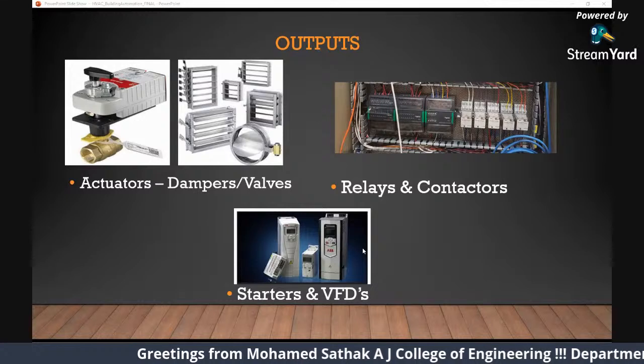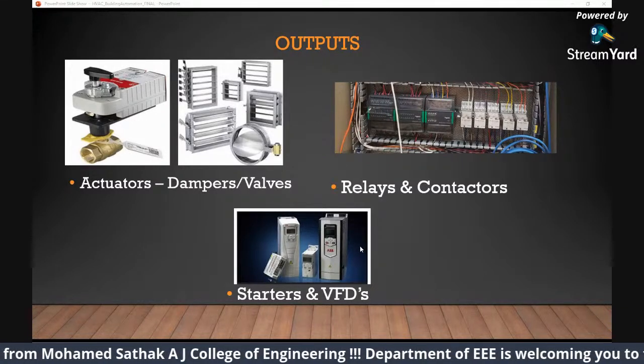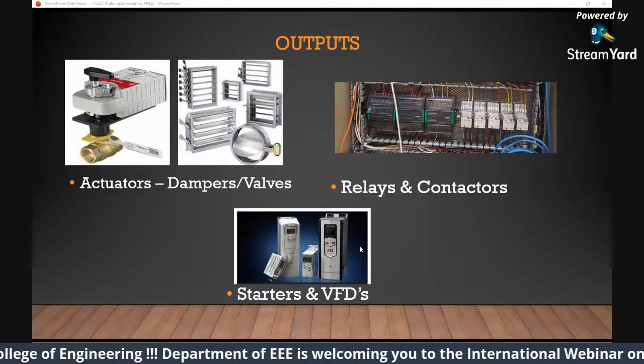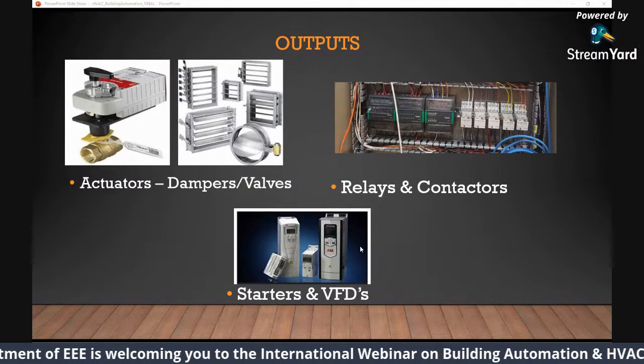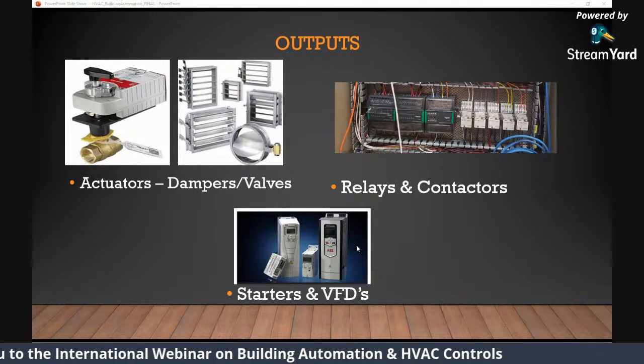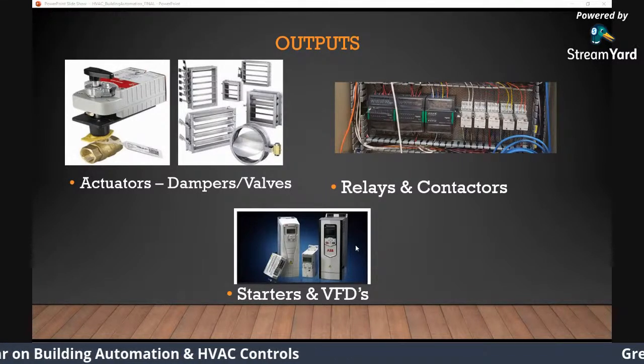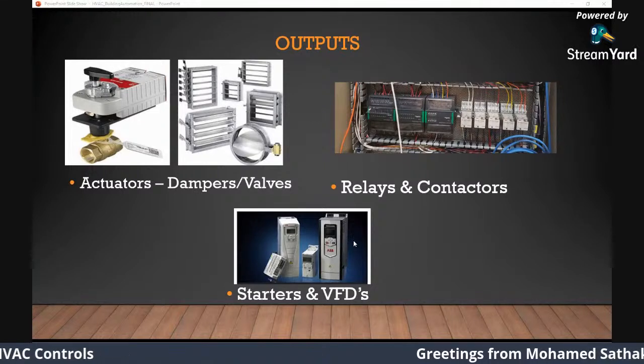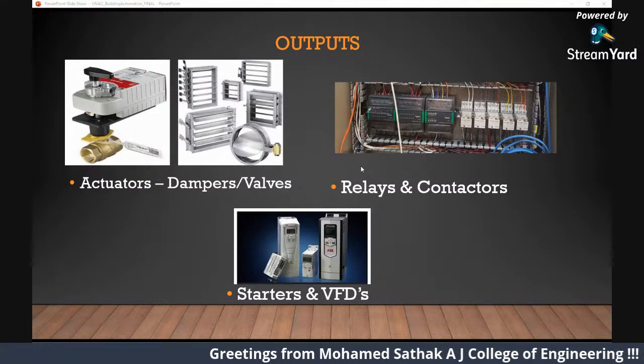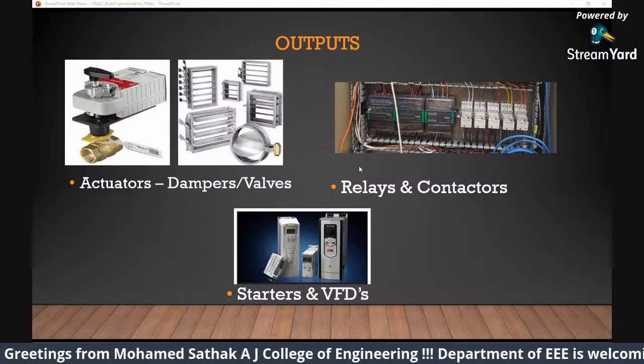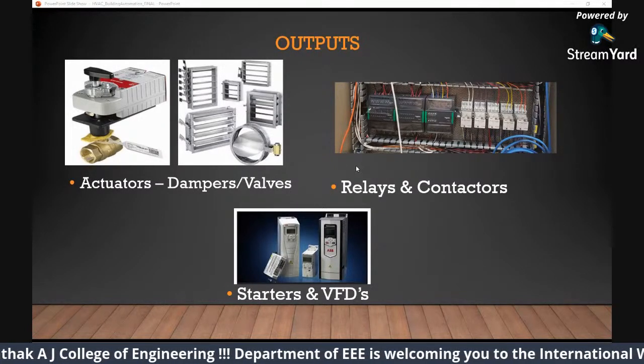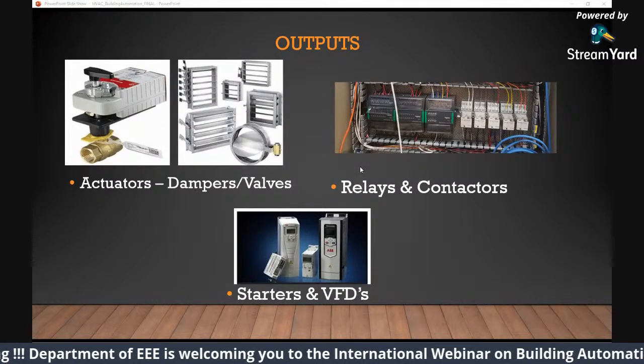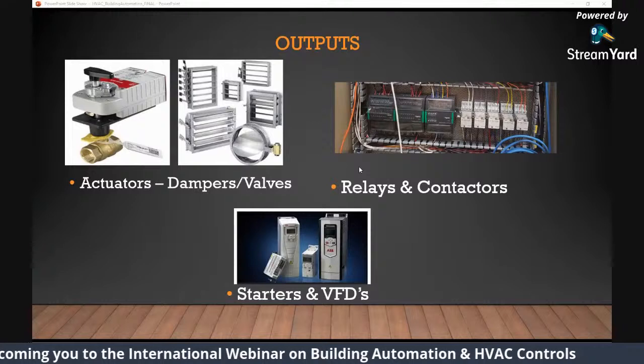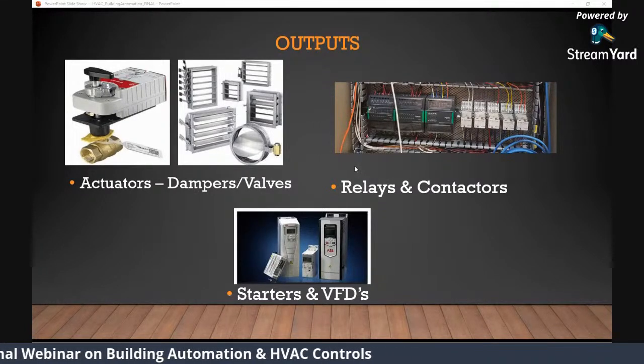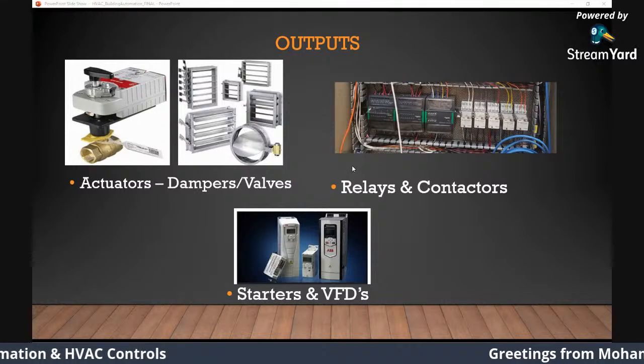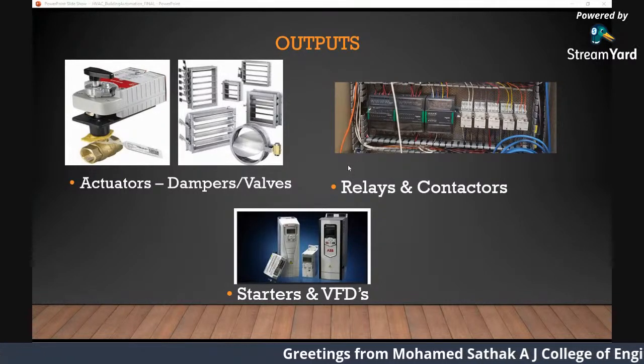Now, what are starters and VFDs? Okay, so in olden days, I mean not olden days, like a few years back, we had starters. Your relays will not go directly to your pumps. There will be an in-between device called a VFD. People from a trade background should have known it. Variable frequency drives control the speed of the pumps and the fans. Okay, so what your controller does is for small equipment, exhaust fans, we turn the fan on and off. That's it. But for pumps and fans which run on high voltage, we do not just use the on and off concept. We adjust the frequency of the pumps, so 0 to 60 hertz, which is done by the controller. We send a 0 to 10 volt signal, which converts into 0 to 60 hertz in frequency, which in turn adjusts the speed of your pumps or your fan.